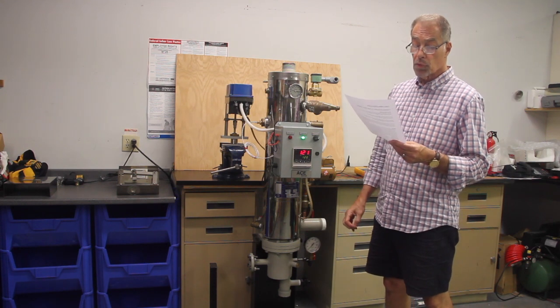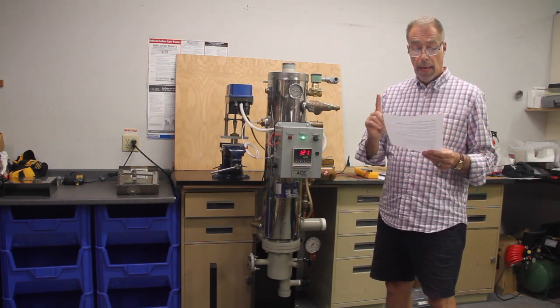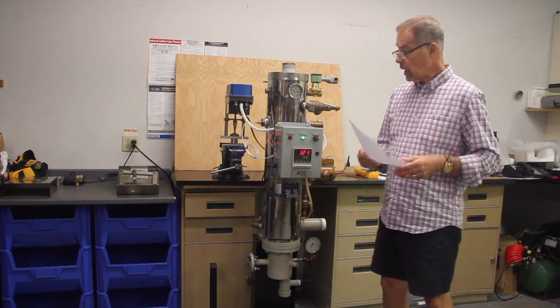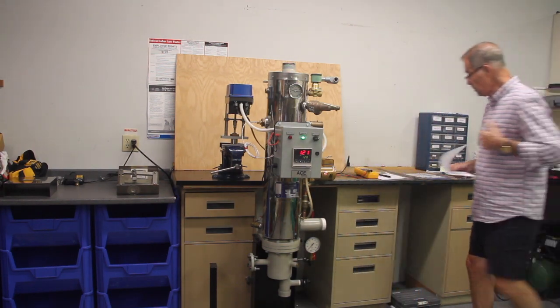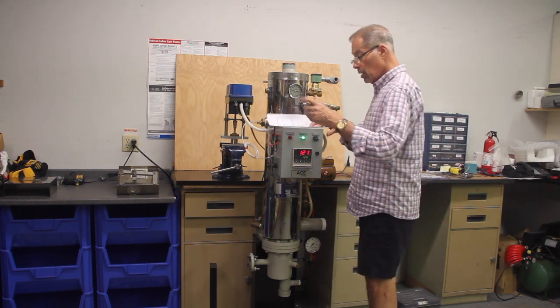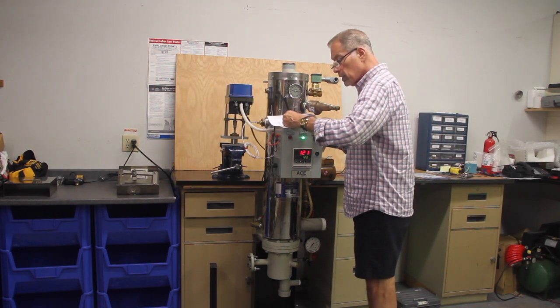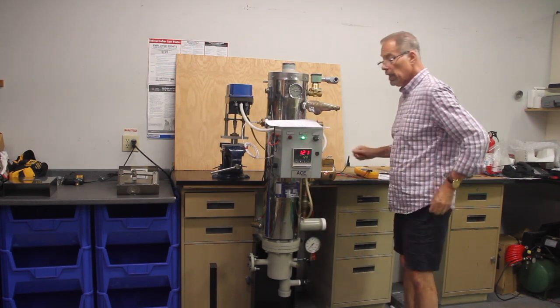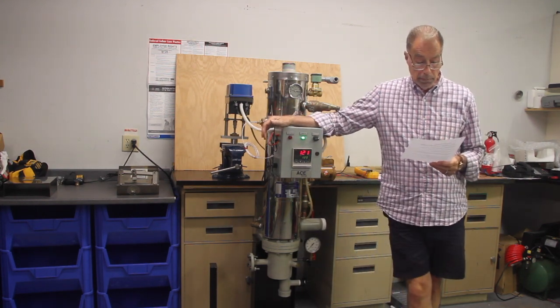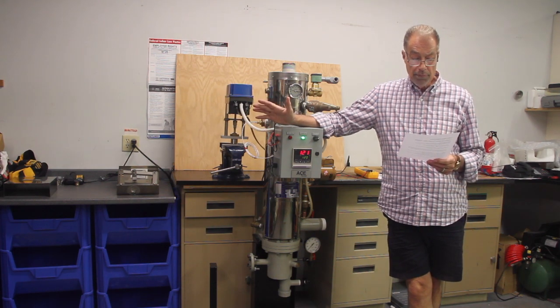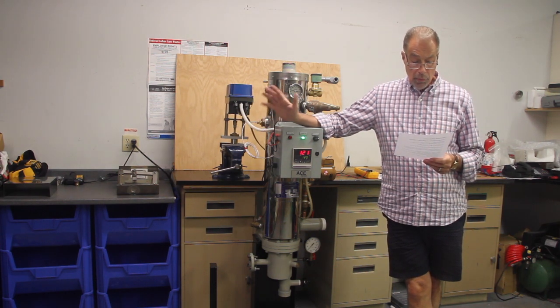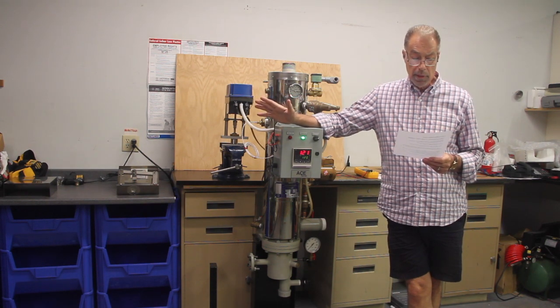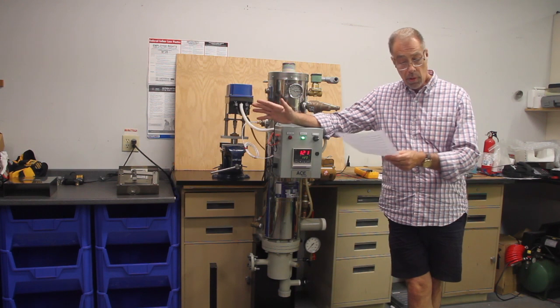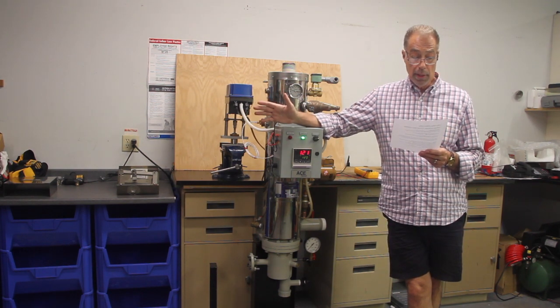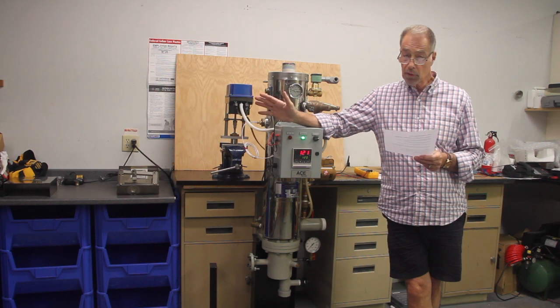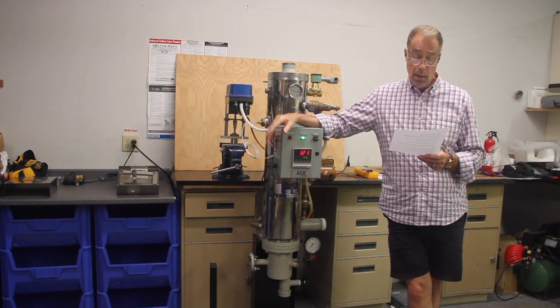The Zamboni is rated for 40 gallons a minute at 120 degree rise. Excuse me, I wrote it down here wrong. We're delivering 160 degree water to the Zamboni heater, to the Zamboni fill, I should say. Again, requiring 25 psi steam. In review, we have a 100 degree rise for the domestic heaters, and then it's blended down to the use temperature, and then for Zamboni it's 40 to 160, and I don't believe it's blended down. I think it's going 160 right into the Zamboni machine.